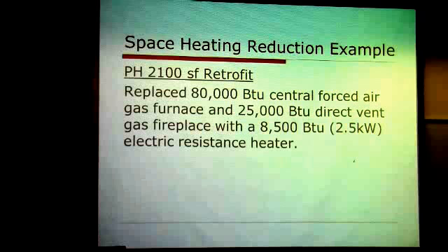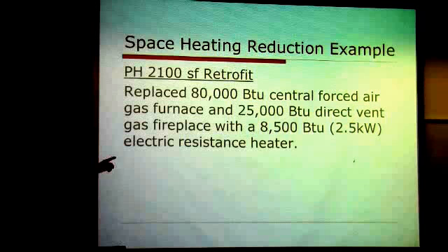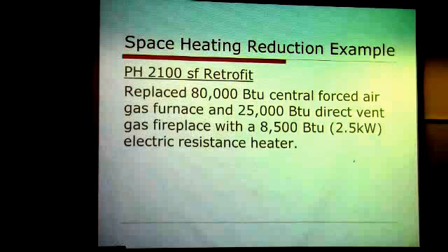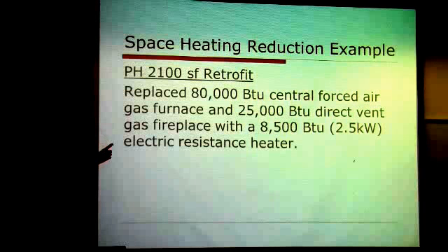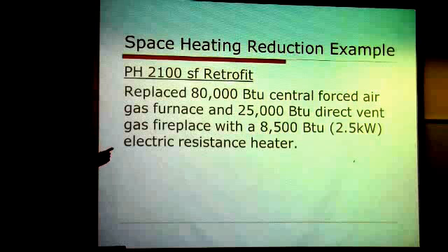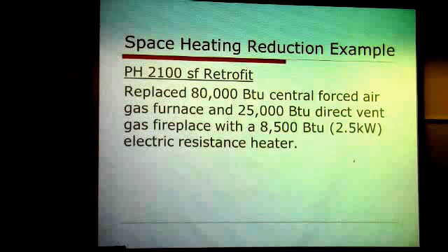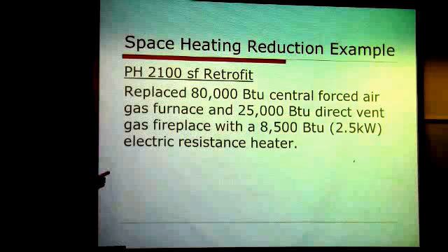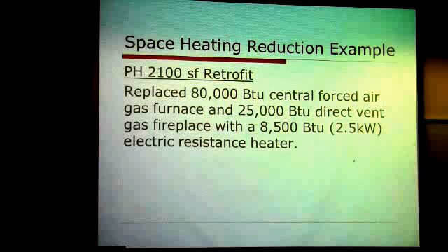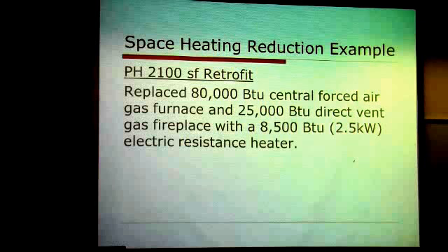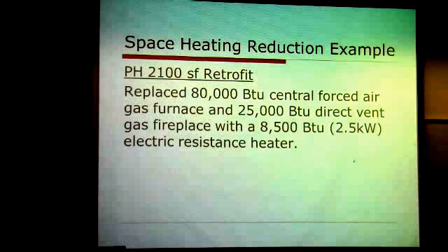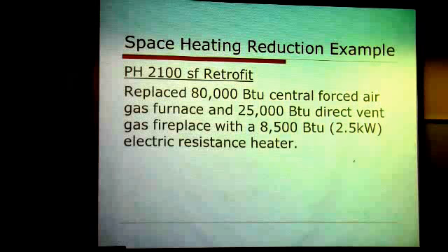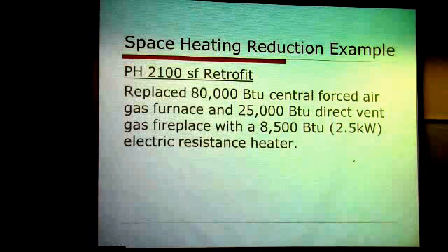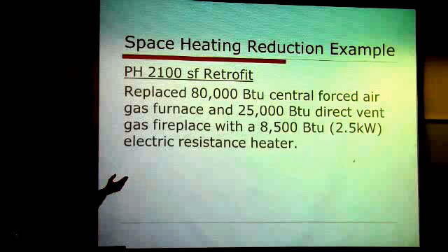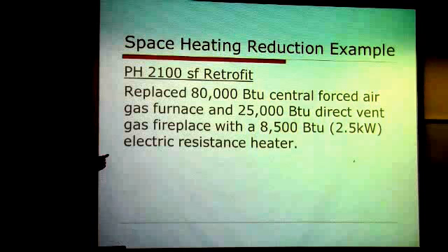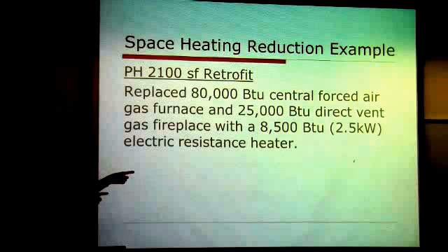And then I just throw the example of that passive house, the retrofit that was 2,100 square feet. Initially, when it was built in 1998, it, of course, had an 80,000 BTU central forced air gas heater system and a 25,000 BTU fireplace. So they were able to get rid of that and only use a 2.5 kilowatt electric heater. They're looking at doing a heat pump, but right at that time they only had money enough to put electric. So even though they're using electric, it's so much less than what they were, it still can pencil out. And you notice it's about 10% of what they used to use.